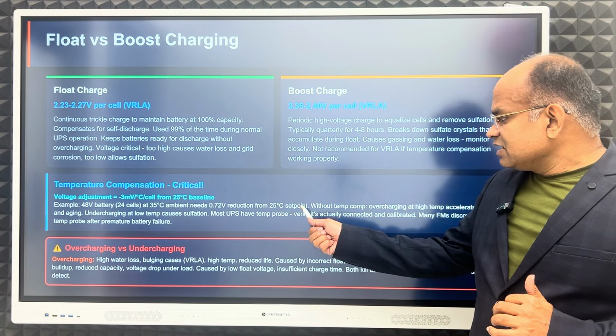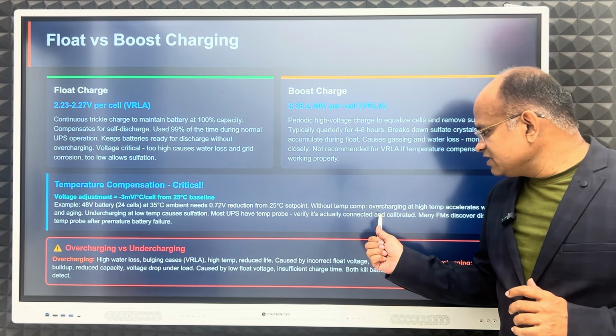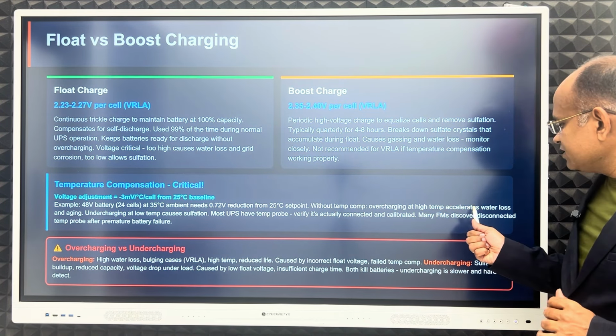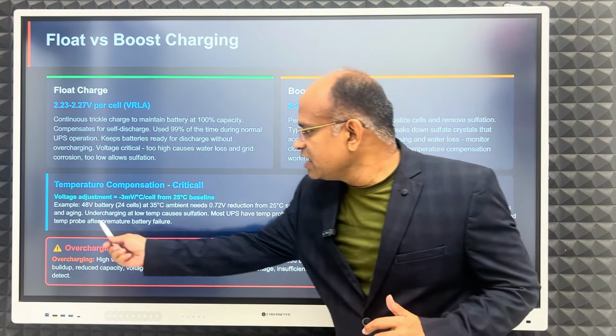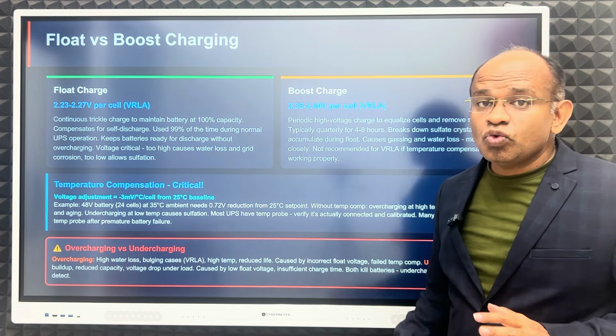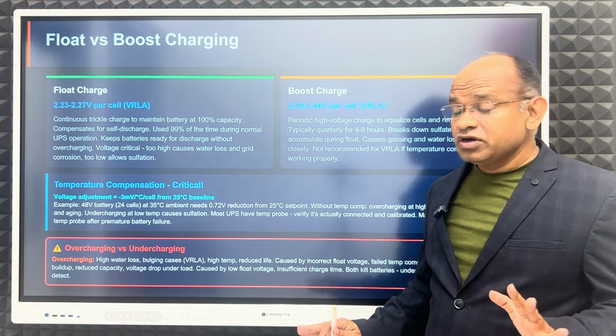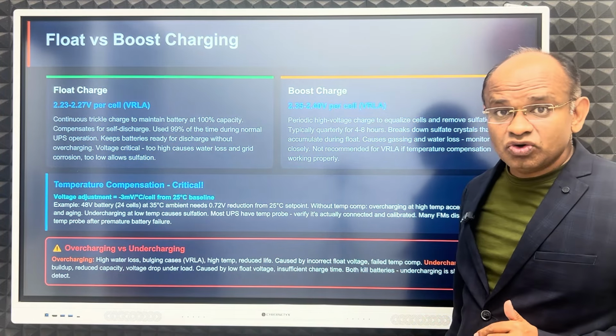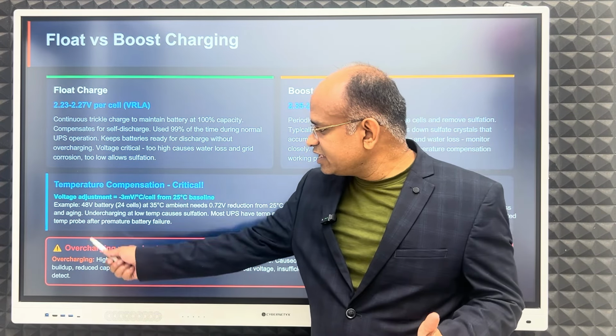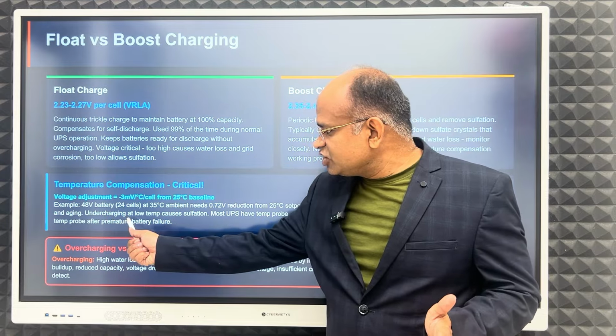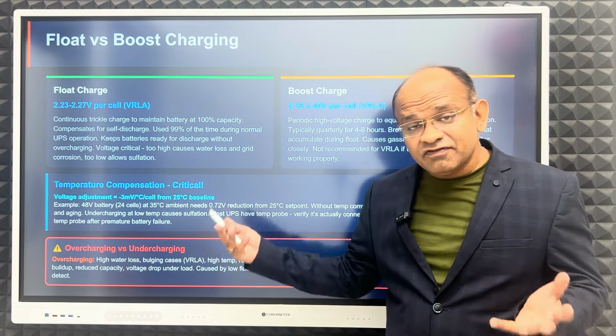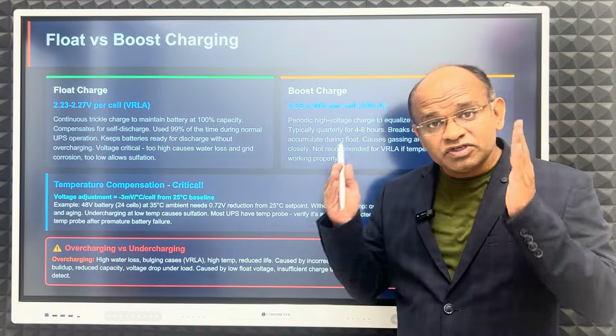Without temperature compensation, overcharging at high temperature accelerates water loss and aging. So over temperature, it will accelerate the aging. Don't do that. Don't increase the voltage. Undercharging at low temperature causes sulfation. Both ways there is a problem, so it should be precise.